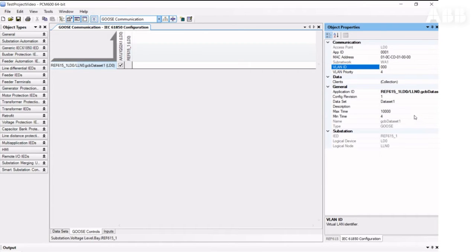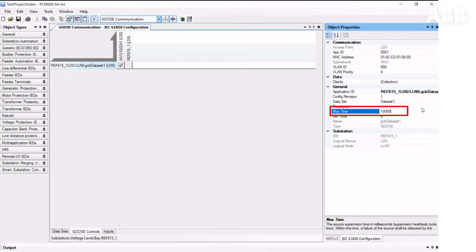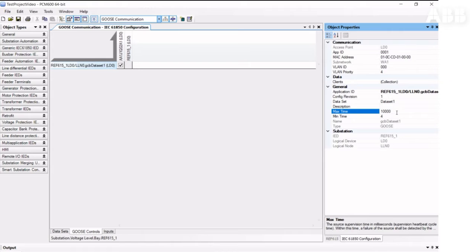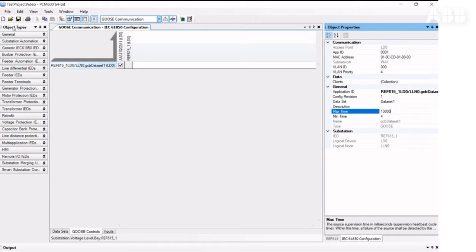Then we can change the maximum time here. The value is 10,000 milliseconds, or 10 seconds by default. It's defined by how often you send GOOSE messages in the network for supervision purposes. Now everything is OK, and we can save and close the tool.